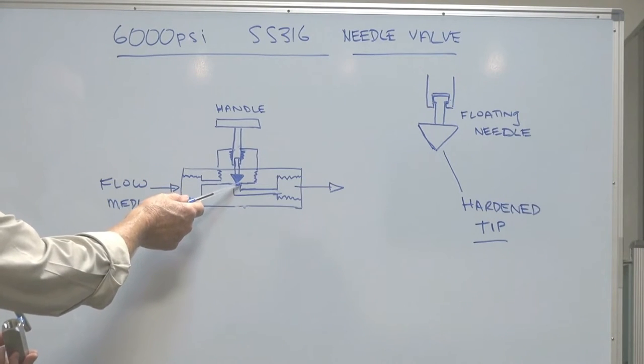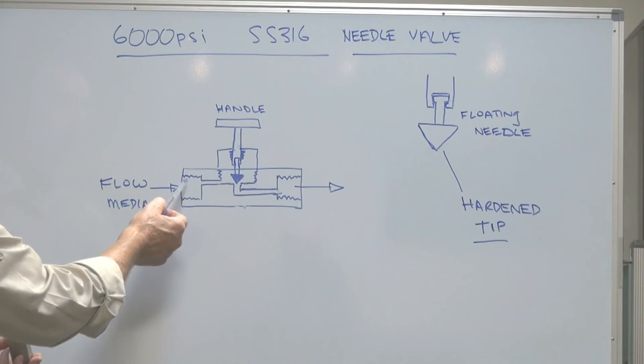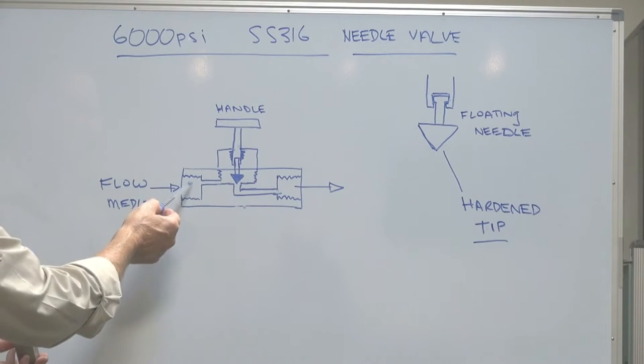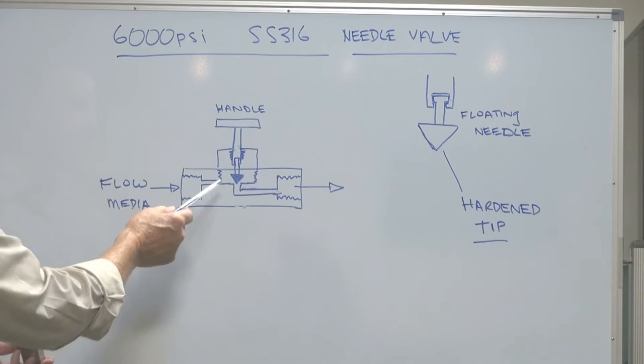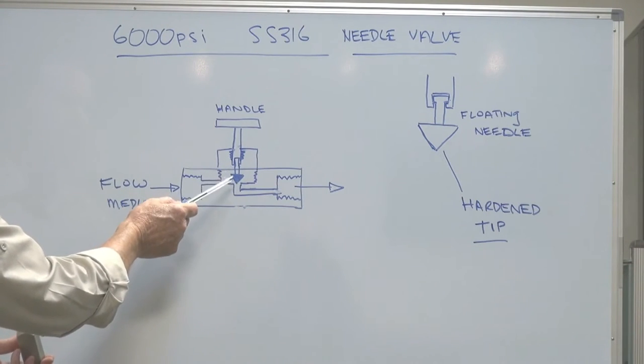This restricts the flow. Even though the actual porting might be a half-inch, three-quarter inch, or one inch, the actual orifice inside might only be five millimeters. It's designed to control a precise flow at very high pressure down to nothing.